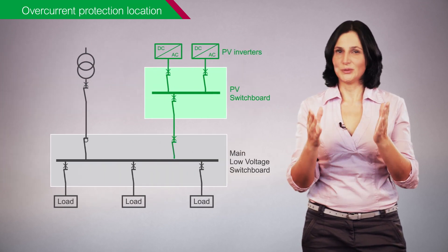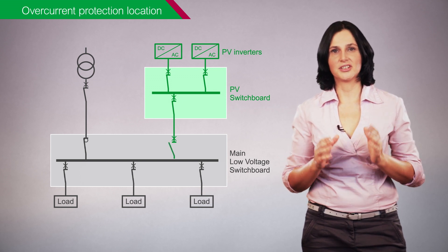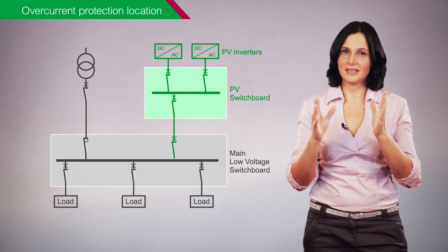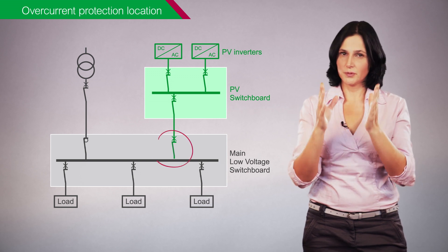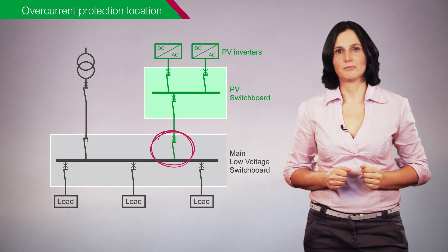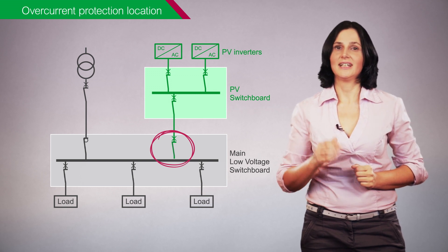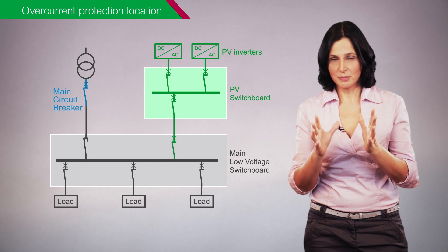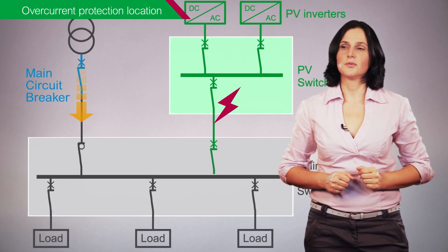Another safety measure is AC overcurrent protection for the photovoltaic power supply system. To isolate electrical faults on the photovoltaic installation, an overcurrent protection device must be located at the point where the photovoltaic system is connected to the building's electrical installation. It's essential to include the overcurrent protection in this exact location to avoid tripping of the main circuit breaker in case of fault in the photovoltaic feeder.